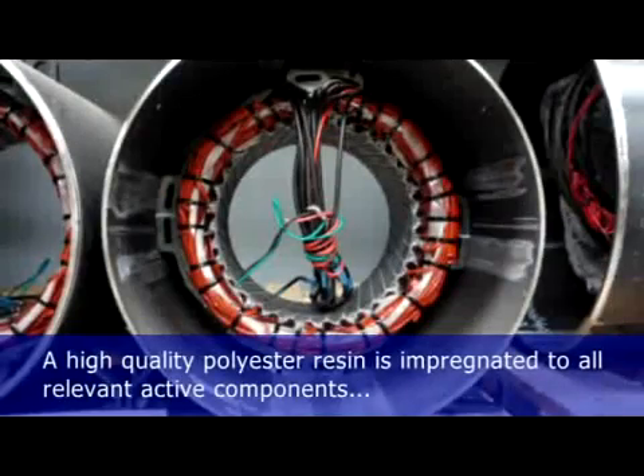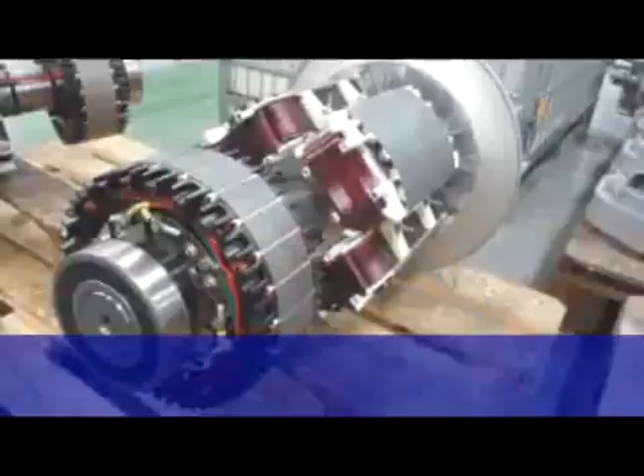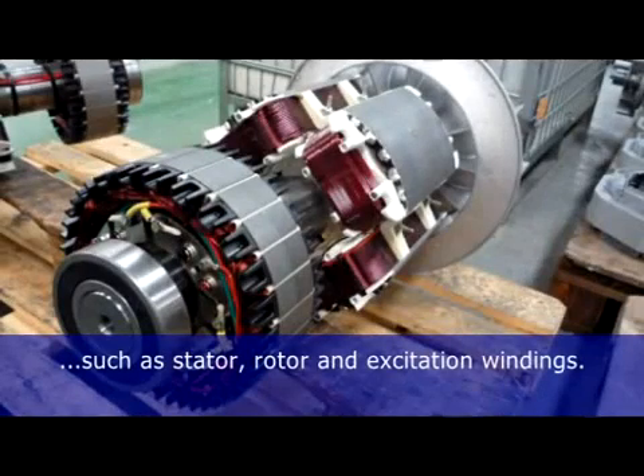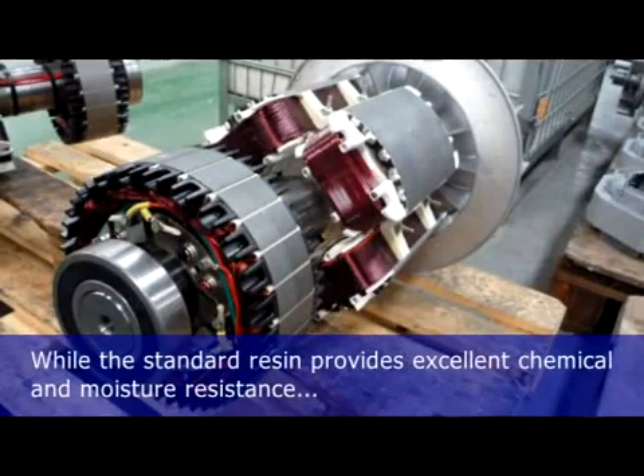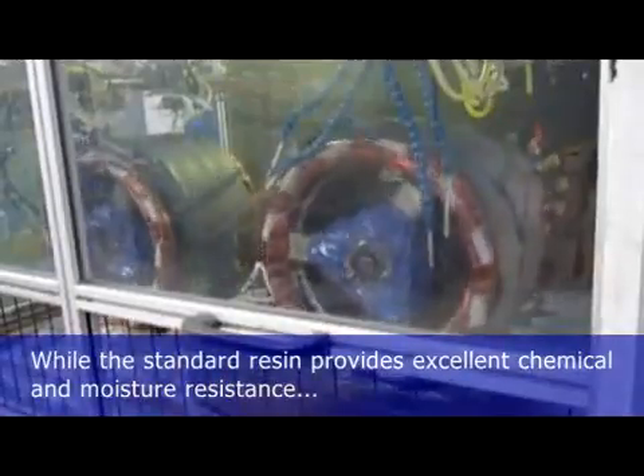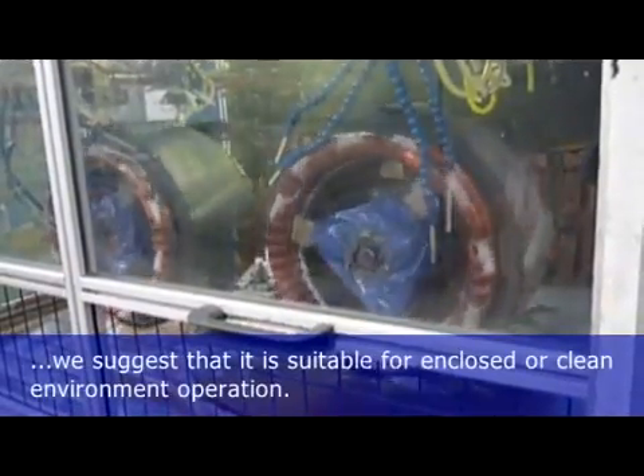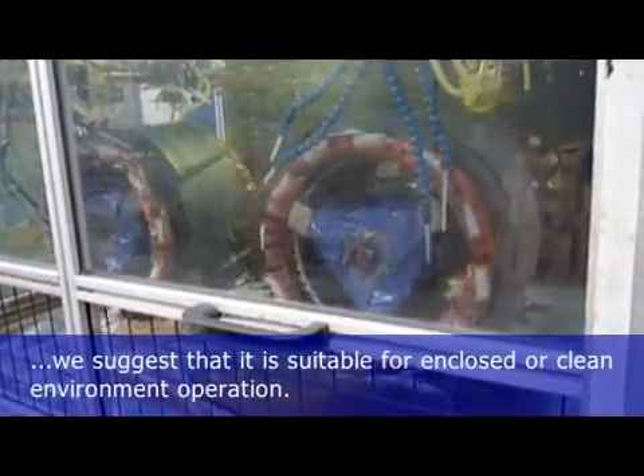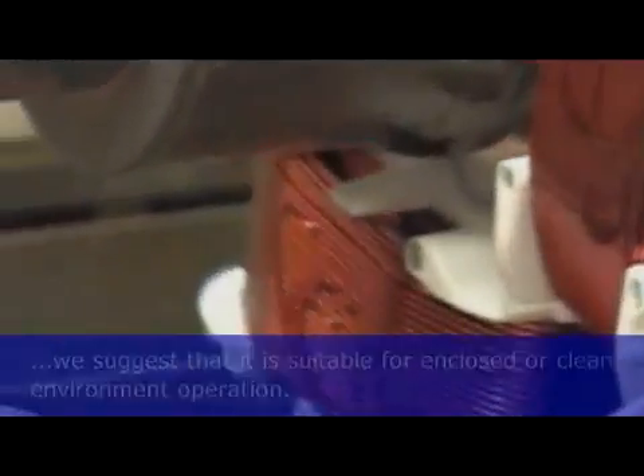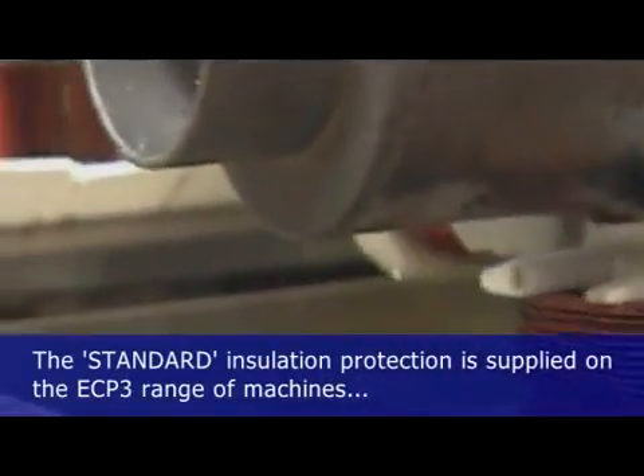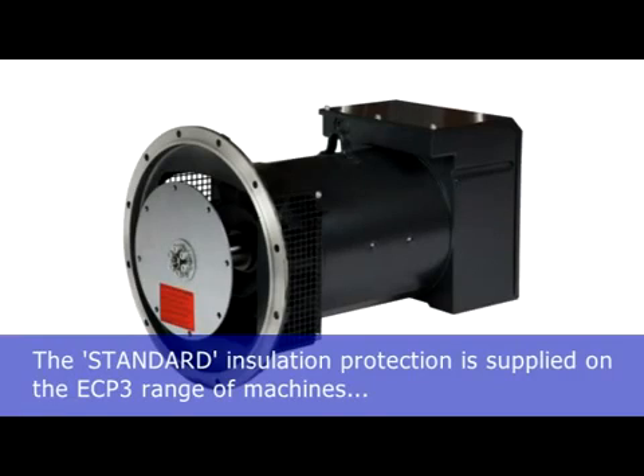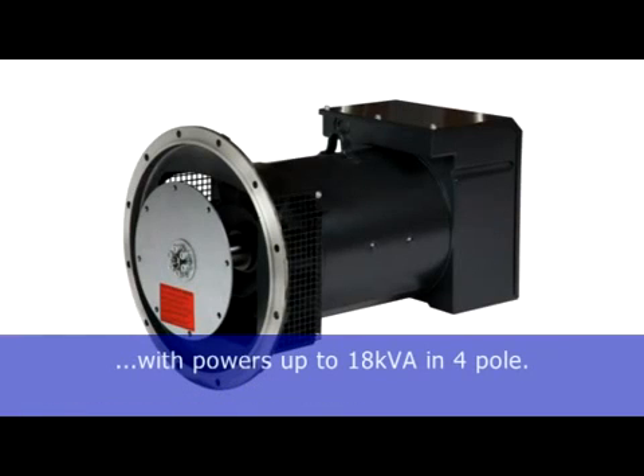A high-quality polyester resin is impregnated to all relevant active components, such as stator, rotor and exciter windings. While the standard resin provides excellent chemical and moisture resistance, we suggest that it is suitable for enclosed or clean environment operations. The standard insulation protection is supplied on the ECP3 range of machines, with powers up to 18 kVA in 4-pole.